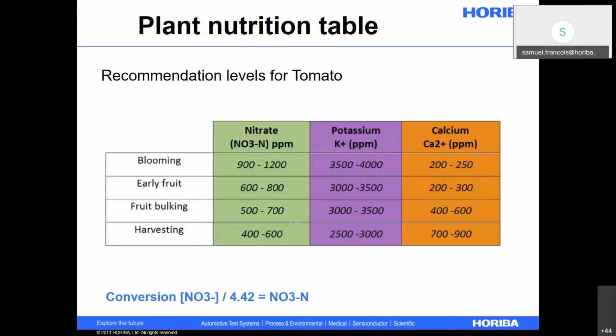Usually, as for accuracy, I would say, and this is not what is written in the manual, but in my experience, it is more around plus or minus 5%, when we compare two different equipment. What is also important for good accuracy is what I just explained about how to do a good calibration and how to do a measurement, but also adjusting the calibration point. For example, if you want to measure very precisely in the 5,000 ppm range of potassium, we supply a solution at 150 and 2,000 ppm.